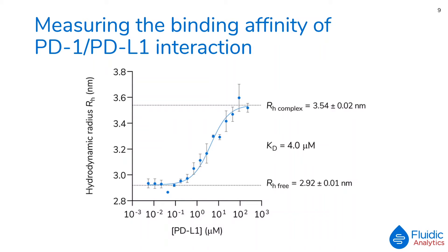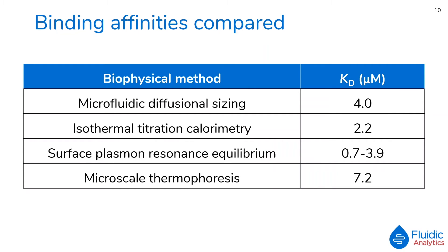The hydrodynamic radius for the unbound protein and the protein complex are also automatically calculated and displayed. The figure on screen shows an equilibrium binding curve obtained by the titration of unlabelled PD-L1 against a constant concentration of Alexa Fluor 488-labelled PD-1. From this, the binding affinity or KD of the PD-1/PD-L1 interaction was determined to be 4 micromolar. Here we show a comparison of binding affinity values for this interaction across a range of biophysical techniques. Microfluidic diffusional sizing on the Fluidity 1W gives a binding affinity value which is in line with those in the literature. Individual references for these values can be found in the application note on our website.